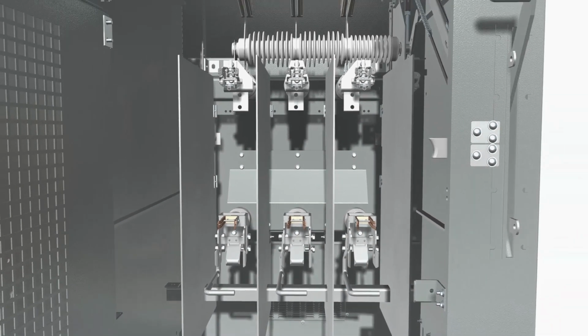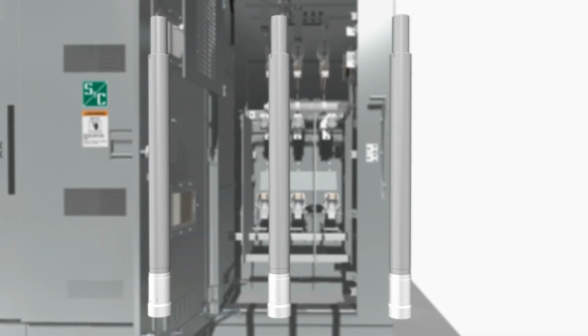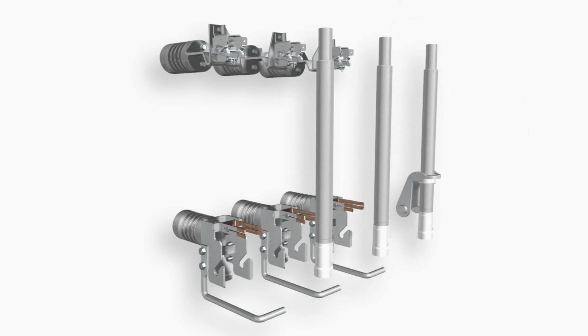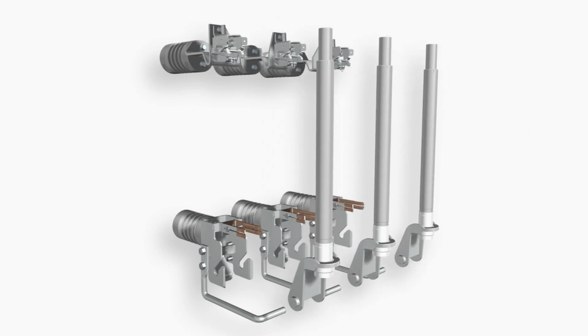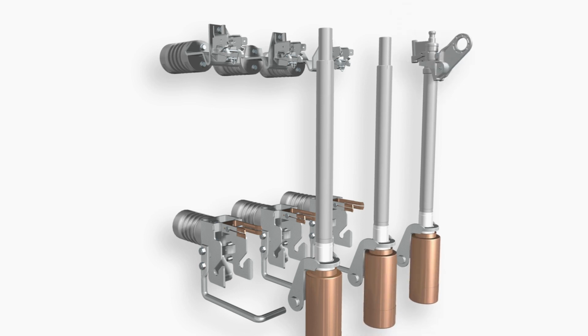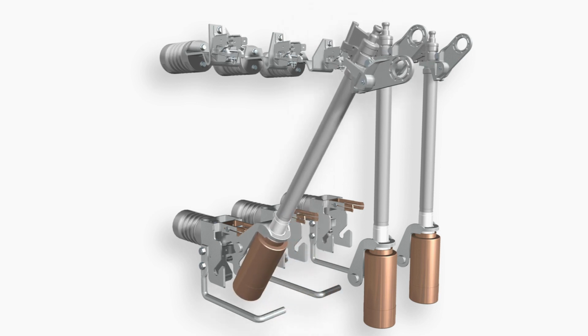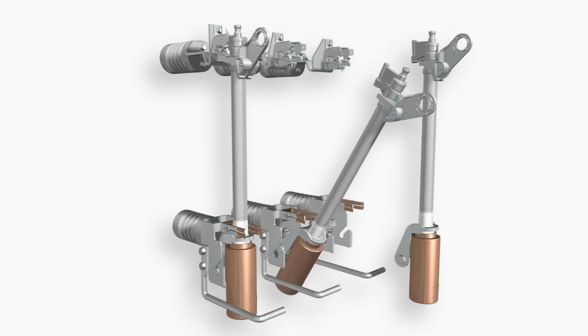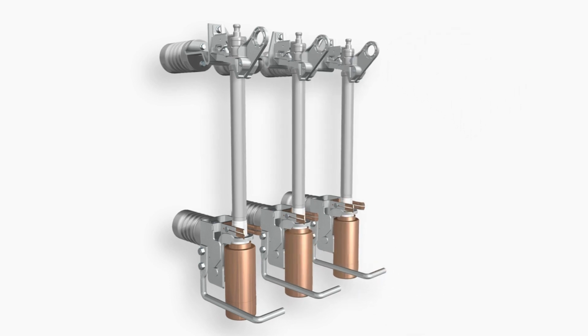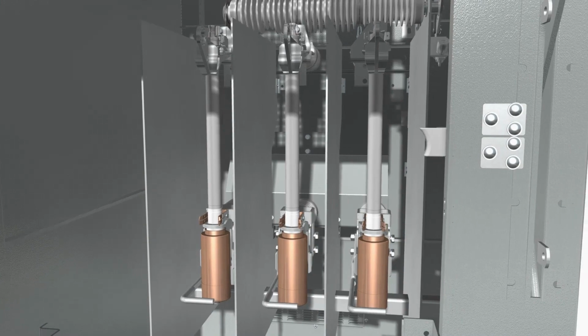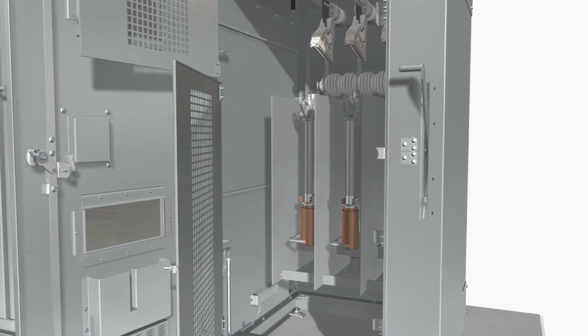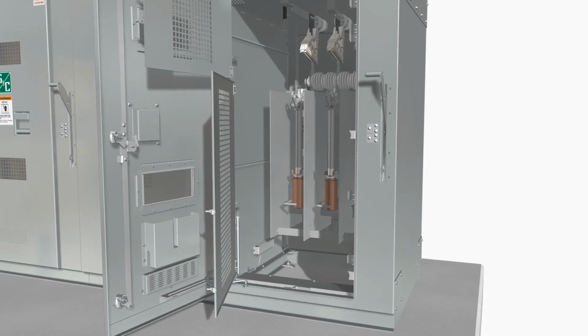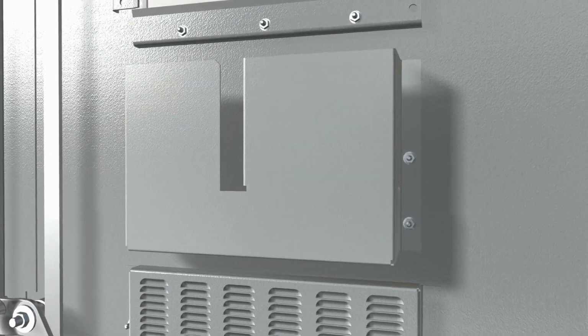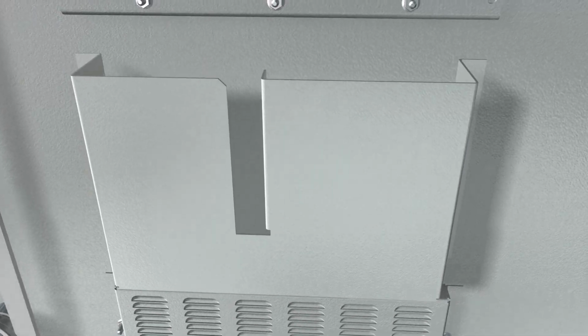Assemble these components following the fusing procedure described in the instruction sheet packed with the applicable fuse components. Install the fuses in the fuse mountings following the procedures described in the S&C instruction sheet about operation that is included with the switchgear for the particular fuse type being used. When installing fuses, make certain complete fuse closure is attained. Store spare refill units, interrupting modules, or fuse units in the container mounted on the inside of the doors to the bays containing fuses or fused voltage transformers.